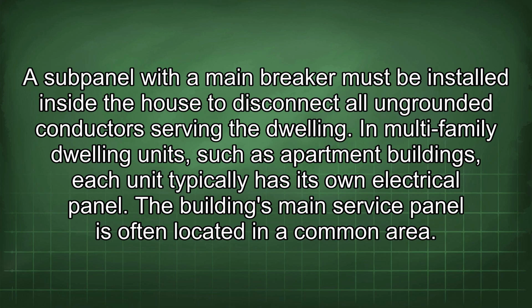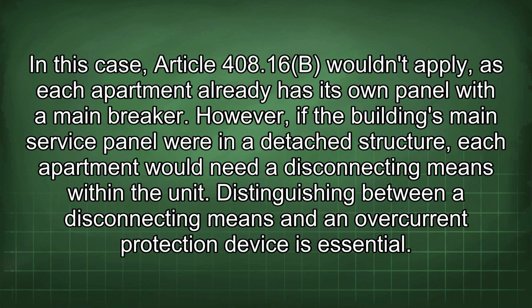In multi-family dwelling units, such as apartment buildings, each unit typically has its own electrical panel. The building's main service panel is often located in a common area. In this case, Article 408.16b wouldn't apply, as each apartment already has its own panel with a main breaker. However, if the building's main service panel were in a detached structure, each apartment would need a disconnecting means within the unit. Distinguishing between a disconnecting means and an overcurrent protection device is essential.